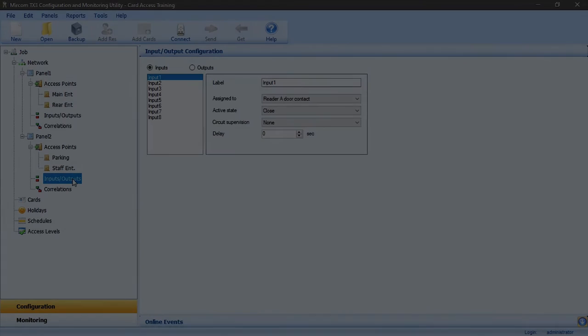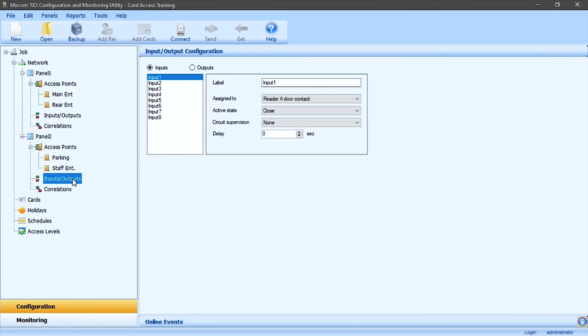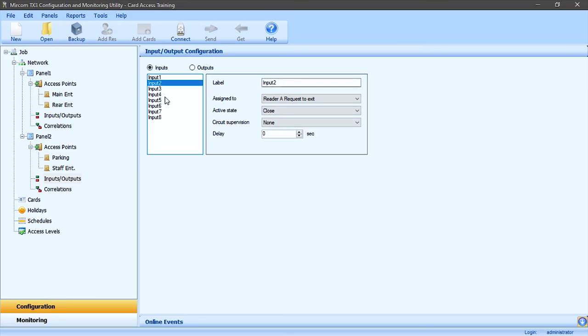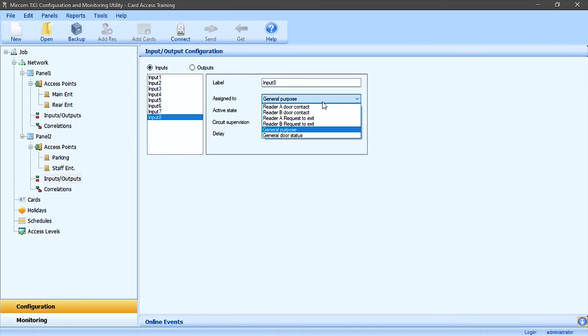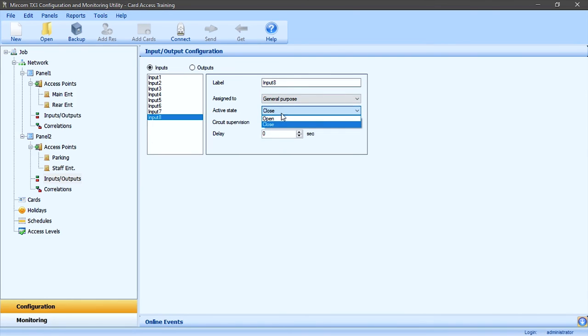Next, I like to configure the inputs and outputs and create correlations for the controller if needed. Inputs 1 and 5 are pre-configured as door contacts for each door. Inputs 2 and 6 are pre-configured as request to exit. Inputs 3, 4, 7, and 8 are pre-configured as general purpose. You can configure each input's assignment, active state, circuit supervision, and delay time as needed.